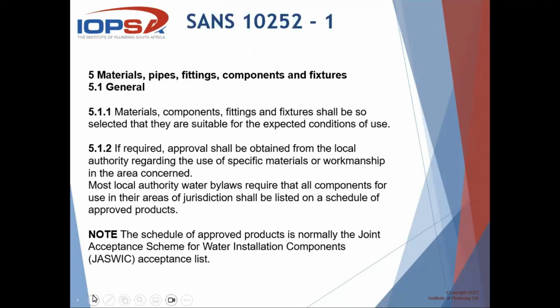Yeah, I think, Gerrie, to kick off, we've had a lot of queries coming across our desk, members phoning through. There seems to be copper pipe that hasn't got any markings. Our members are asking, is it compliant pipe? The wall thickness of some of the pipes seems extremely thin, and they're asking for guidance: what should we be looking for? Is there anything they could do just to verify? I think today's session is basically that. We're going to have a look at what we have come across, and then also provide some guidance as to what plumbers can look at in order to ensure they're installing the correct pipe.